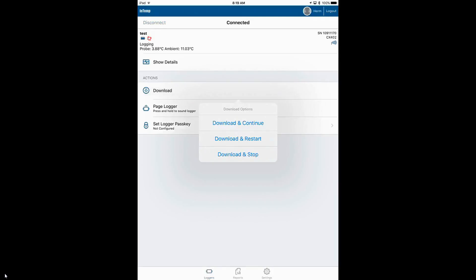If you want to redo the configuration, maybe move the logger to a freezer or something like that, you would click on download and stop. We're just going to download the data and let it continue logging.